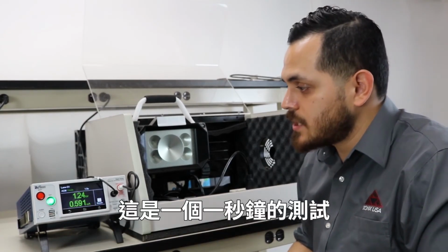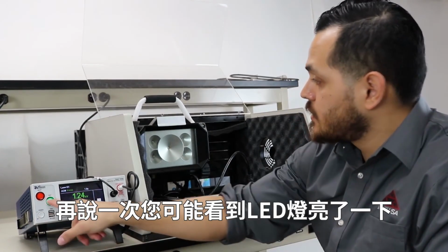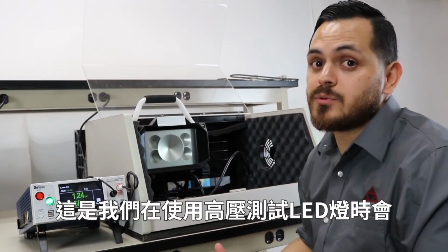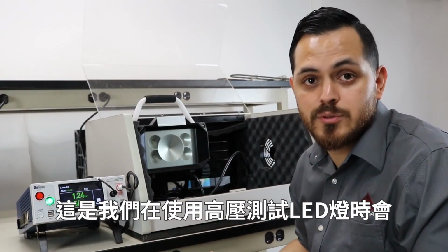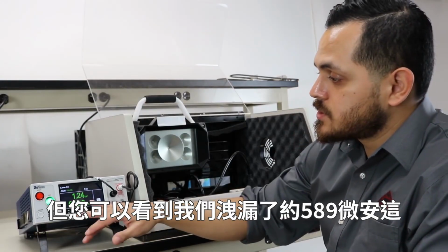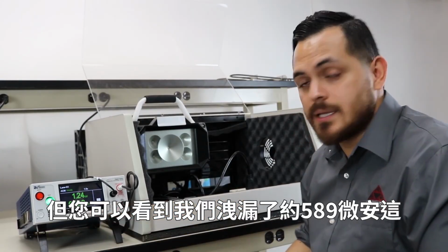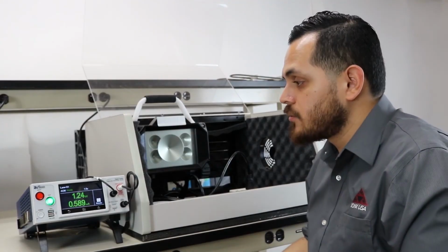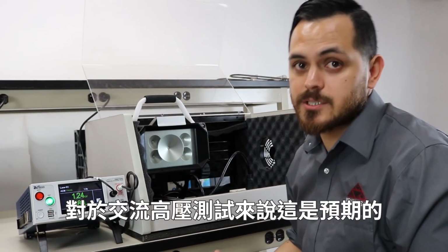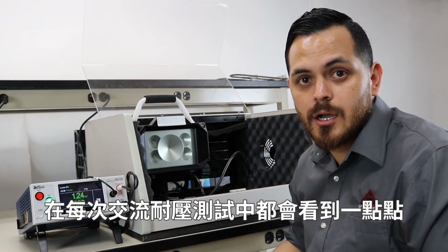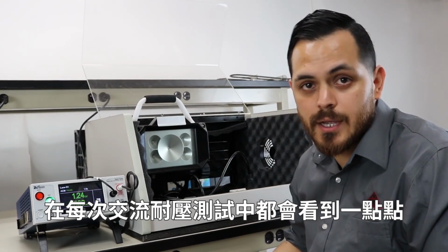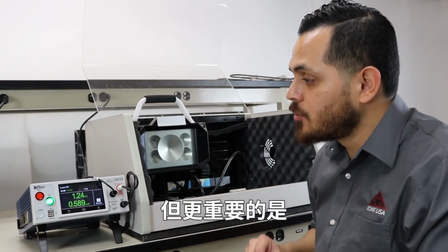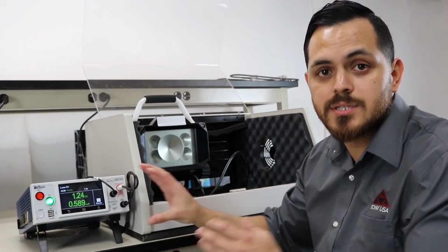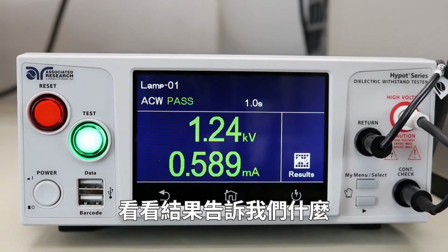This is a 1 second test. Again, you may have seen the LED actually turn on a little bit, which is something we see with LED lamps when Hipot testing. But you can see we leaked about 589 microamps, which again, for an AC Hipot test, that's expected. A little bit of reactive current is to be seen in every ACW test. But more importantly, we can kind of zoom into the screen and see what the results are telling us.